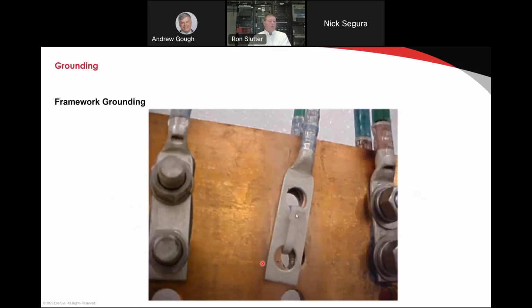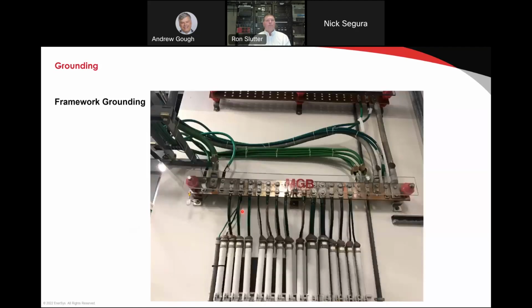What do you see that's wrong with this? Well, obviously, there's some problems here, right? Tie wrap's not going to cut it. Excuse me. We have back-to-back fittings. We have fittings without an inspection port. We have too much grease being utilized. We have no lock washers on these connections here. We have short barrel fittings. All of these are generic, typical installation issues that we see with this picture.